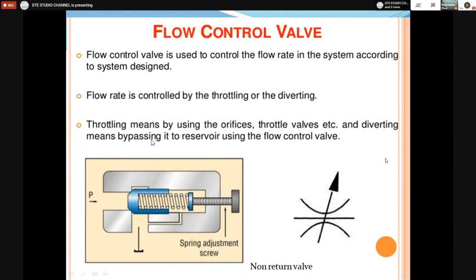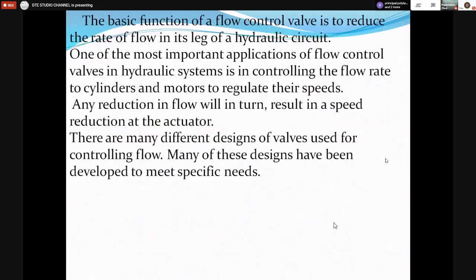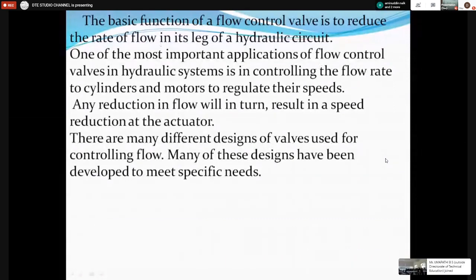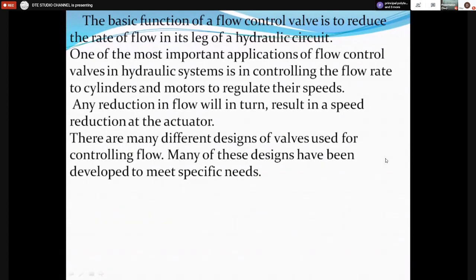There are two methods of changing the rate of flow: by throttling — opening or closing the screw — or by diverting some fluid to the reservoir. The basic function of a flow control valve is to reduce the rate of flow in a leg of the hydraulic circuit. One of the most important applications of flow control valves in hydraulic systems is controlling the flow rate through cylinders and motors.